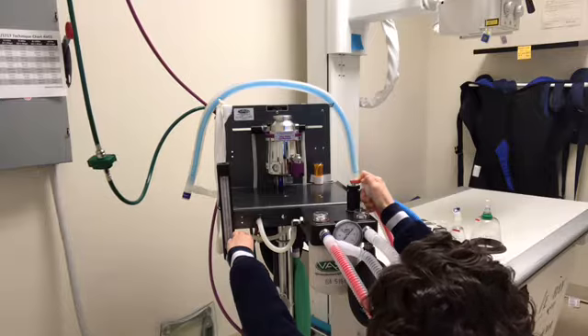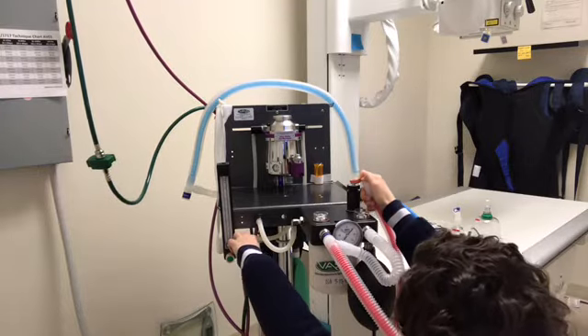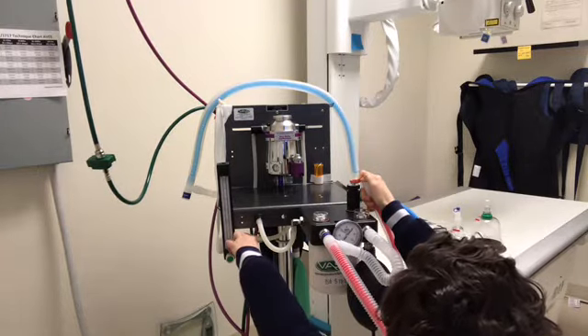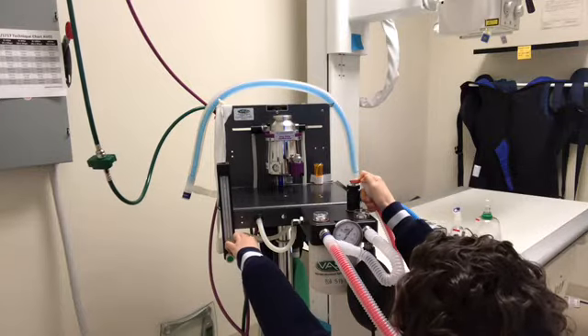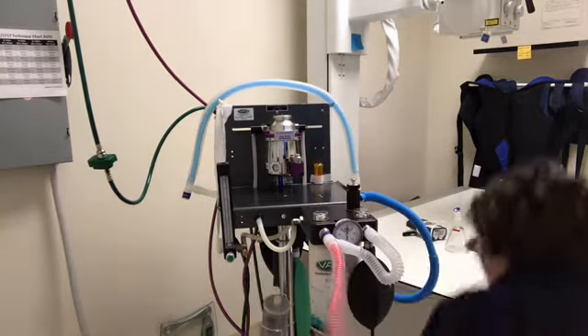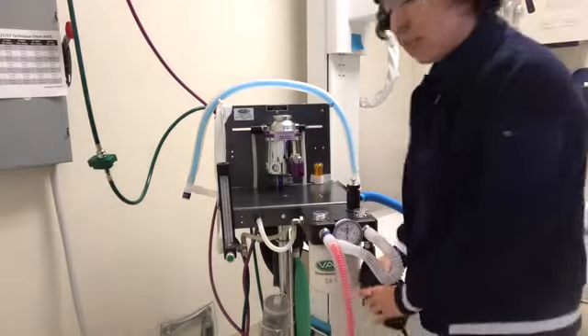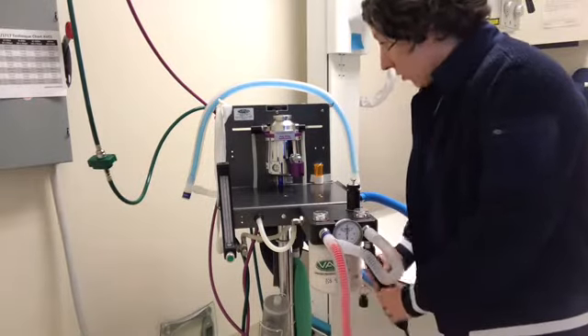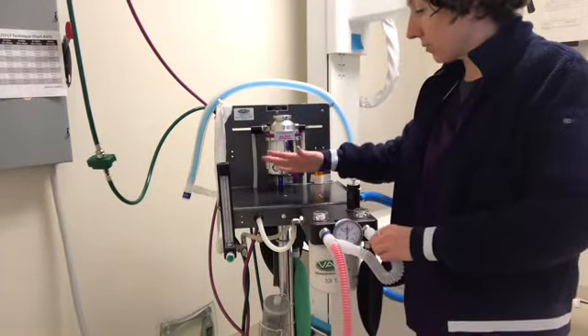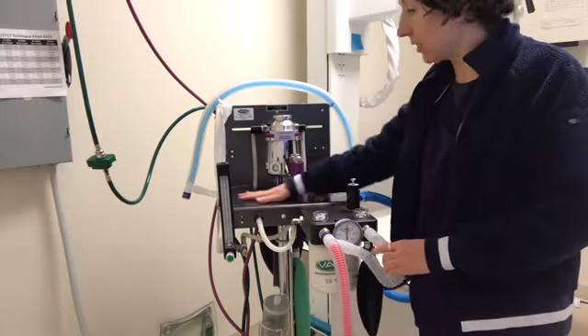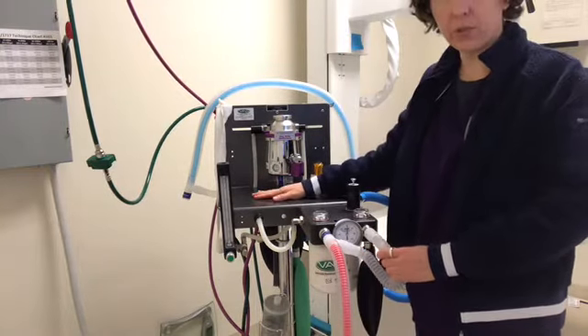Okay, and you want to hold it for about 5 seconds. And as you can see, it dropped 1 centimeter in the entire time that I've been talking here. So that means that it has a good seal on everything. So this was a good leak test. So this machine is in good working order and ready to be used.